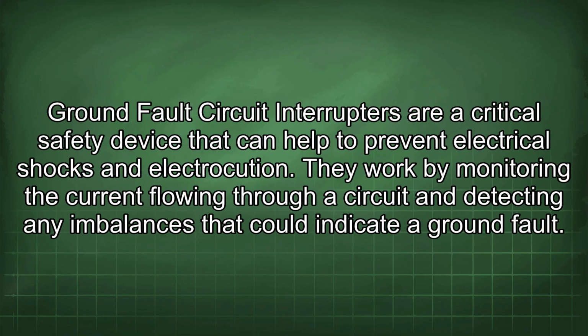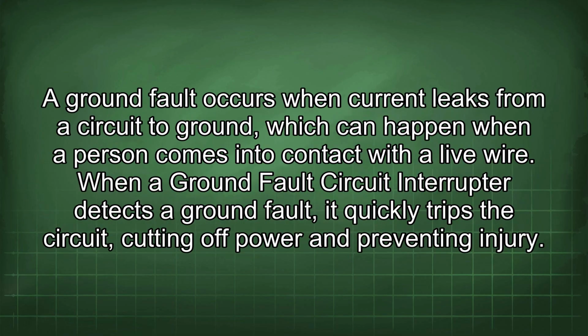Ground fault circuit interrupters are a critical safety device that can help to prevent electrical shocks and electrocution. They work by monitoring the current flowing through a circuit and detecting any imbalances that could indicate a ground fault. A ground fault occurs when current leaks from a circuit to ground, which can happen when a person comes into contact with a live wire. When a ground fault circuit interrupter detects a ground fault, it quickly trips the circuit, cutting off power and preventing injury.